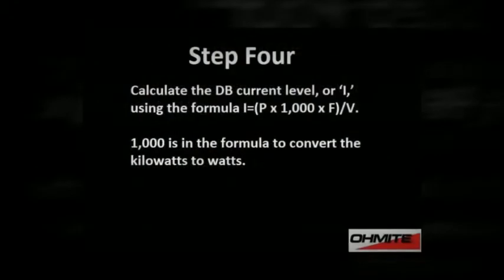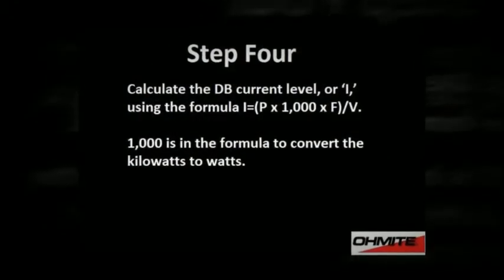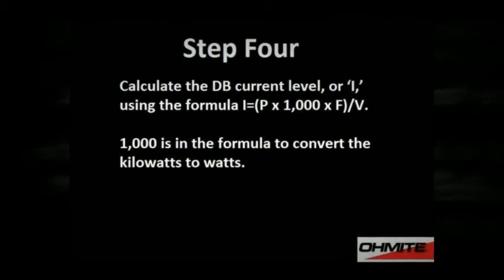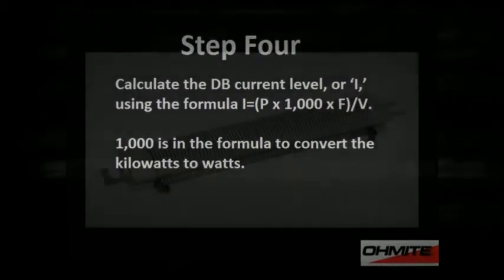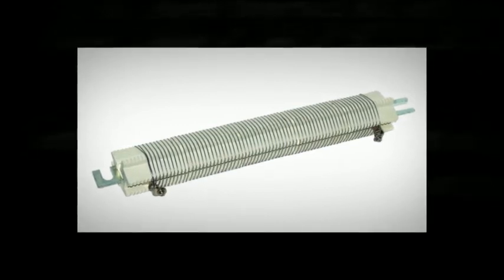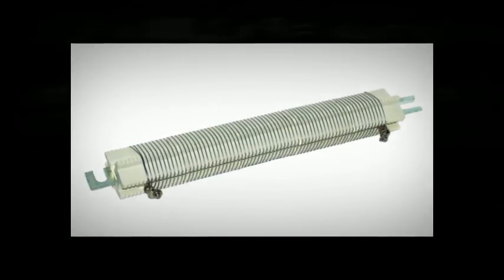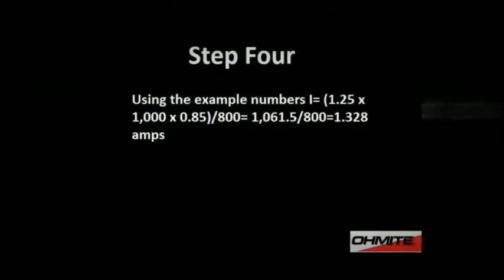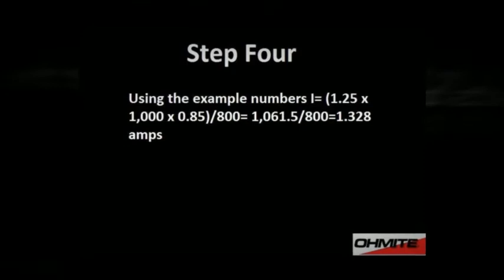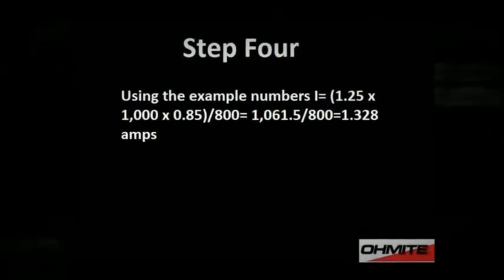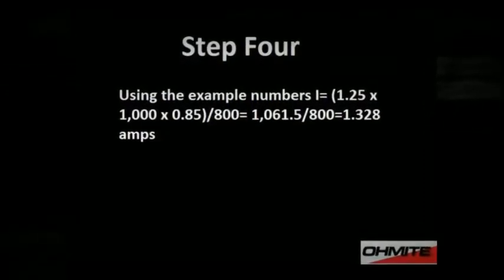Then, calculate the DB current level, or I, using the formula: I equals P times 1,000 times F, divided by V. The number 1,000 is in the formula to convert kilowatts to watts. Using the example numbers, I equals 1.25 times 1,000 times 0.85, divided by 800, equals 1,061.5 divided by 800, equals 1.328 amps.